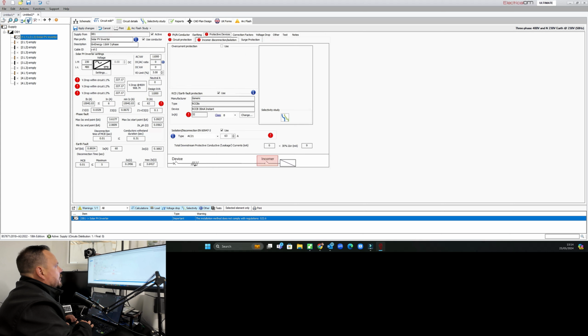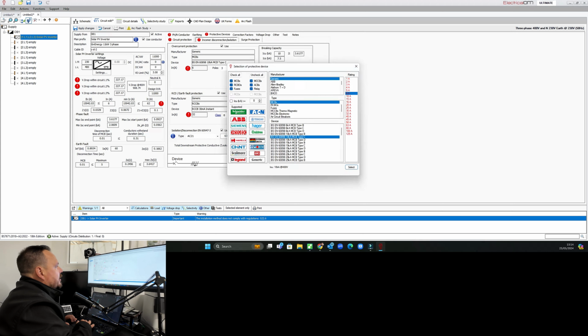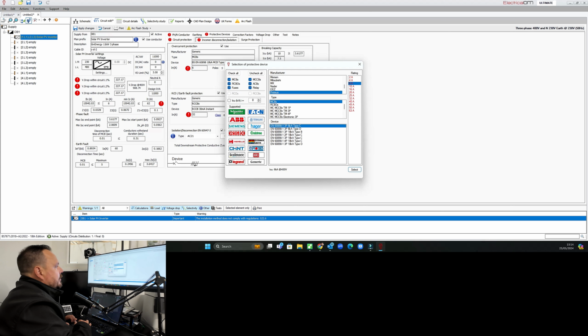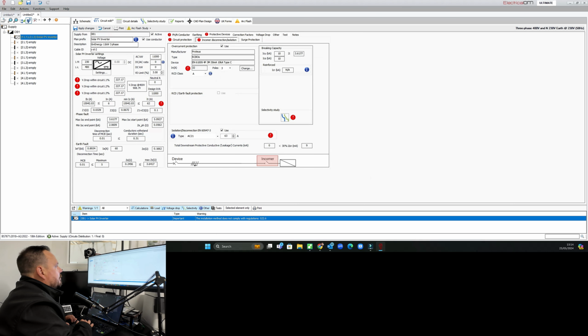So now we need to go to our protective devices, and we're going to use those in this case, and we'll change that using Proteus breakers, and we're going to be using RCBOs. C-type, and these are the 3 module 4 poles, and we'll set that to 32 amps, and it's a class A, type A overcurrent protective device. I've just realised I put that to 11,000 rather than 11 kilowatt. That'll help things out a little bit better.